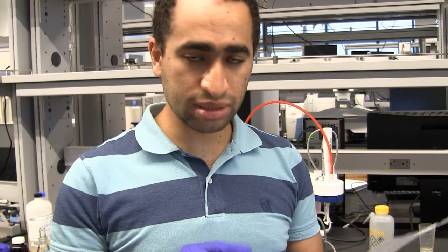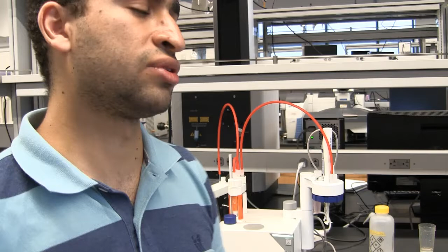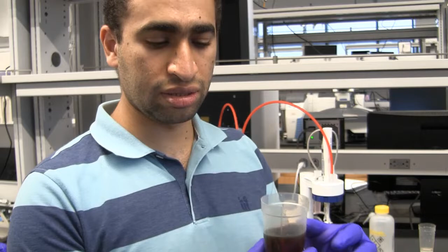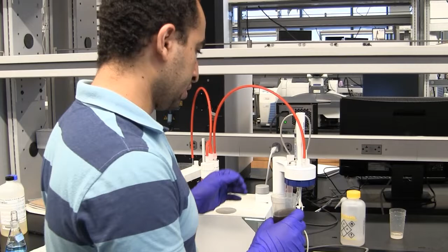If it's a base number, the crude oil that we're going to add is 7 divided by the expected base number, and you will find it in the SOP. And if it's an acid number you're trying to measure, it also depends on your expected acid number. So you will have a table, and based on this table you will decide which mass of oil you need to add to your 60 ml of solvent. So in our case, we're expecting a very low acid number, so we added 10 grams of crude oil to the 60 ml of solvent, and then we are going to test that. So let's add it in here.